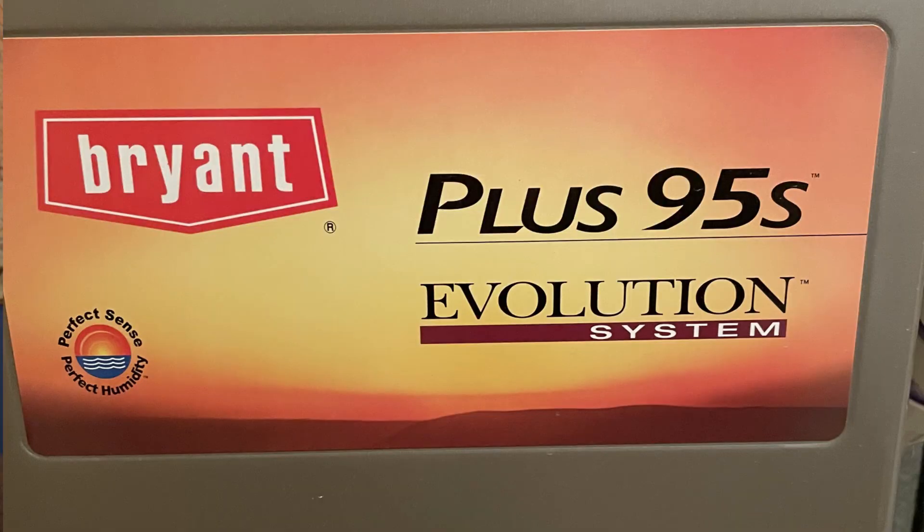The system that does the bedrooms has a SEER 13 air conditioner with an 80% efficiency furnace. The one that does the living space has a SEER 13 AC unit but a 95% efficient furnace. My dad keeps the bedrooms set several degrees lower than the main living space, so that main 95% efficient furnace heats the vast majority of the house — he estimates only about 10% of the heat comes from the other unit because it just doesn't come on very often.